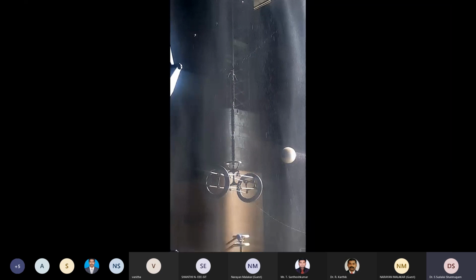So we will create artificial rain in the laboratory. There is equipment called rain-making equipment, which can simulate actual rain within the laboratory itself. After creating the rain, we usually switch on the equipment at least 10 minutes before the experiment so that the entire insulator surface is wet with water. After that we apply the voltage, and we see up to what voltage under wet weather conditions the insulator can withstand. Mind you, I am showing only the power frequency withstand and flashover here, both dry and in wet condition.